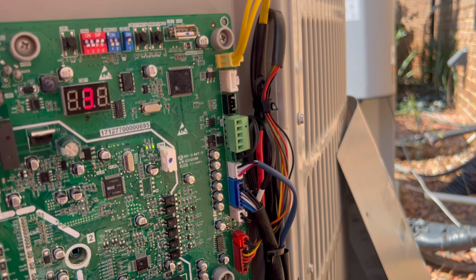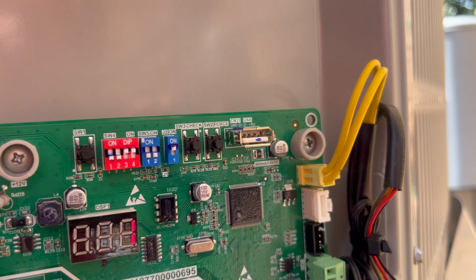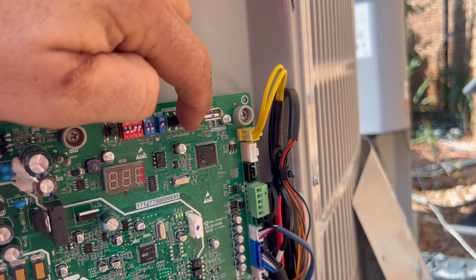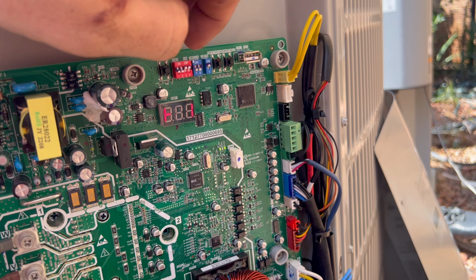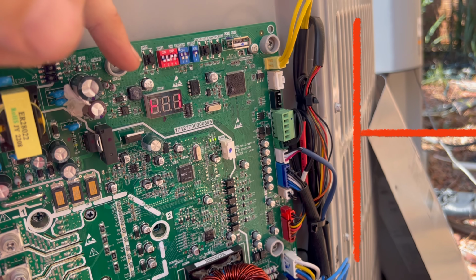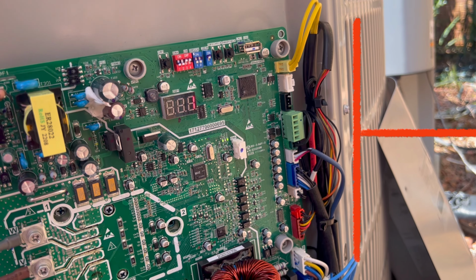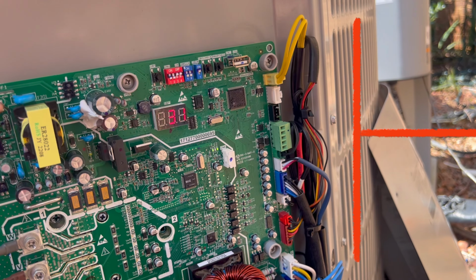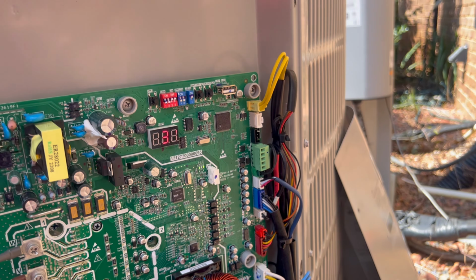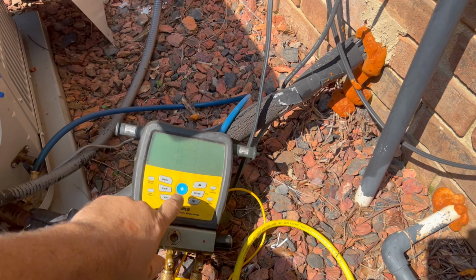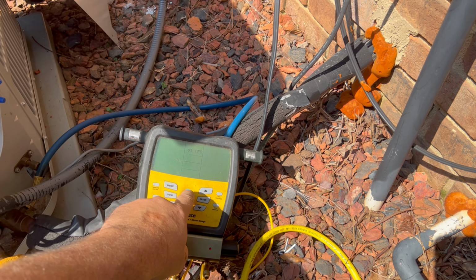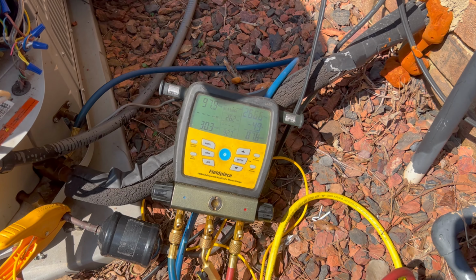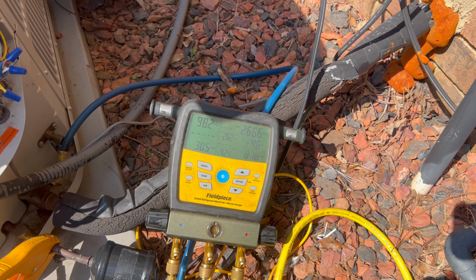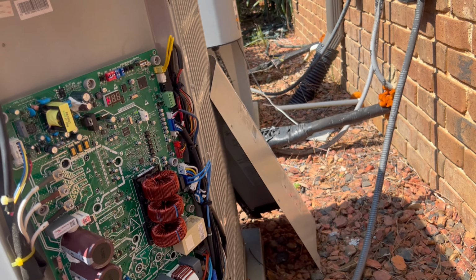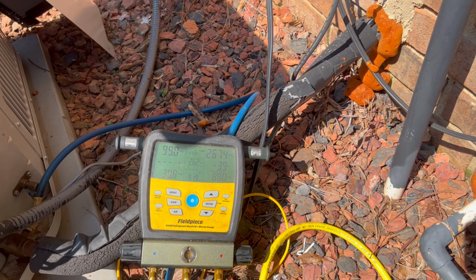The way you do that is these two little buttons up here. You see the one on the right says force. Just press that for a second or so and release, and you see that funny little symbol. Again, I don't know if it comes out real well, but it's a straight line with a little dash over. That puts it into forced charging mode, and naturally my manifold turned off. So now we'll let that run for a second. And once it starts picking up into charging mode, we'll see what it's actually doing when it's running 75% and higher.